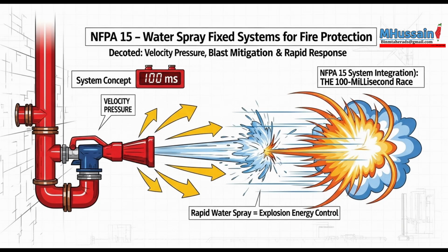This is where the standard really demands rigor, separating maybe the experts from the novices. It really does. First off, hydraulic calculations are mandatory. You have to determine the required pressure and flow at every single nozzle. That's 8.1.1. No skipping corners there. Yeah. And those nozzle pressures have minimums. For outdoor hazards where you've got wind, evaporation concerns, the minimum is 20 psi, about 1.4 bar. And Annex A.8.1.2 wisely recommends bumping that up to 30 psi for small orifice nozzles, like 3/8-inch or less.